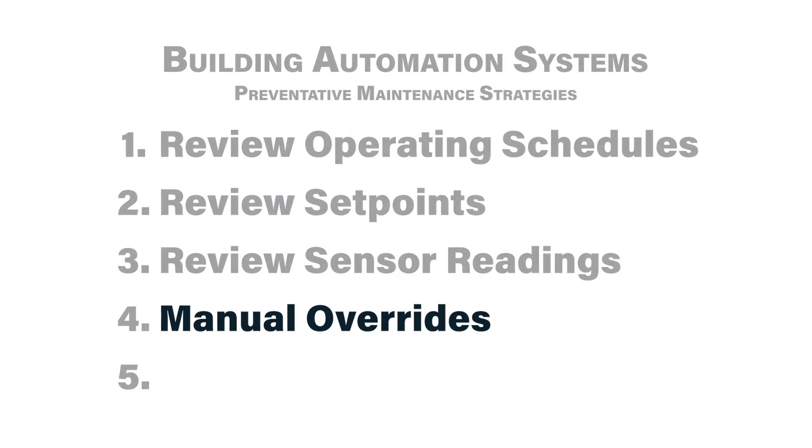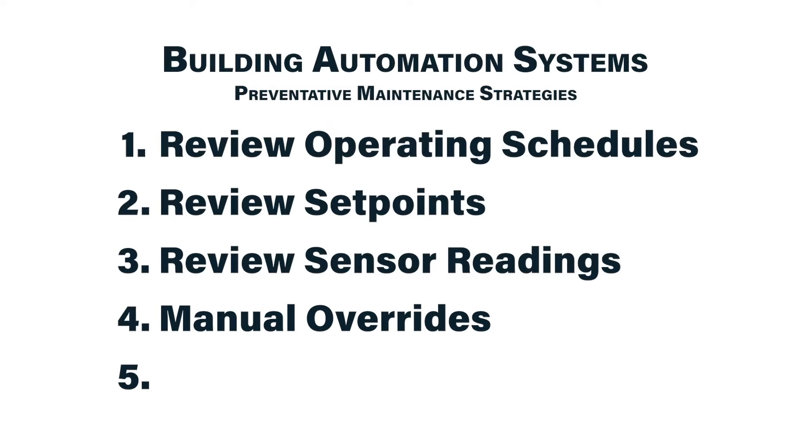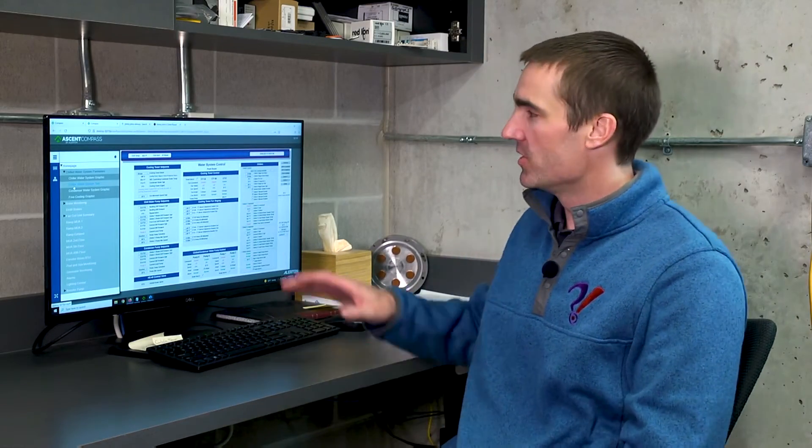The fourth task you should be performing on your building automation systems is to occasionally review the graphics for overrides on certain pieces of equipment. Now, using a building automation system's user interface to override certain pieces of equipment on or off, or certain valves open or close, despite what the sequence of operation is calling for, is a functionality that gives great flexibility to the building operator.